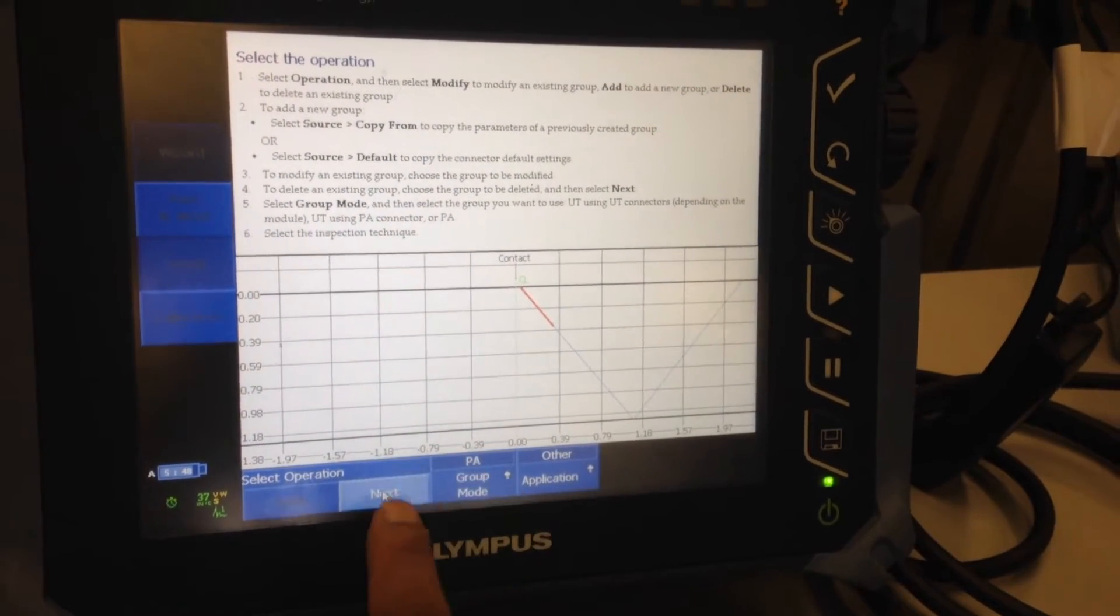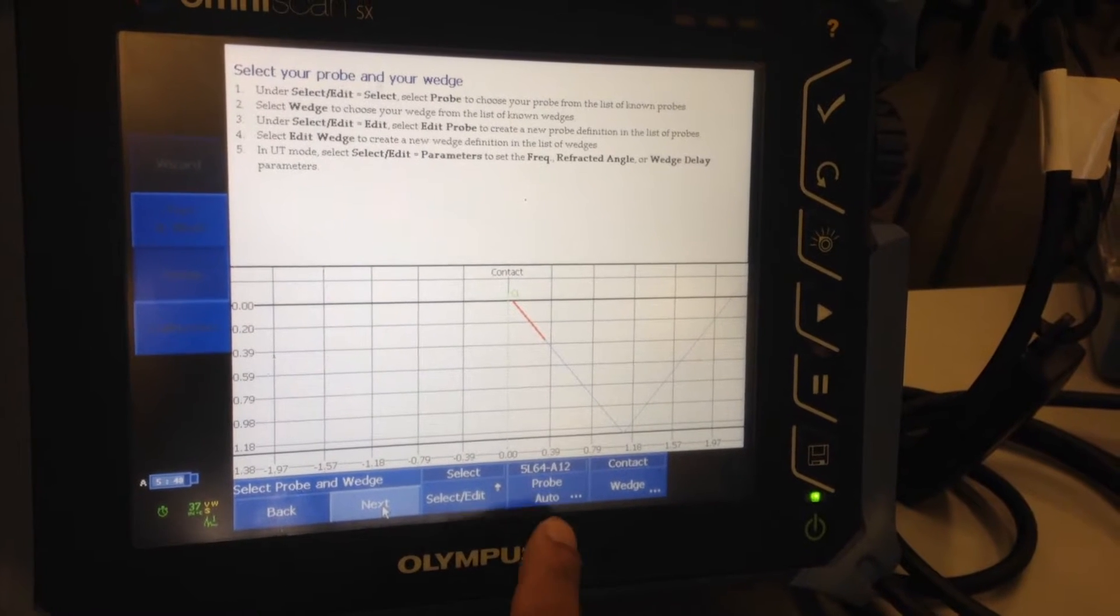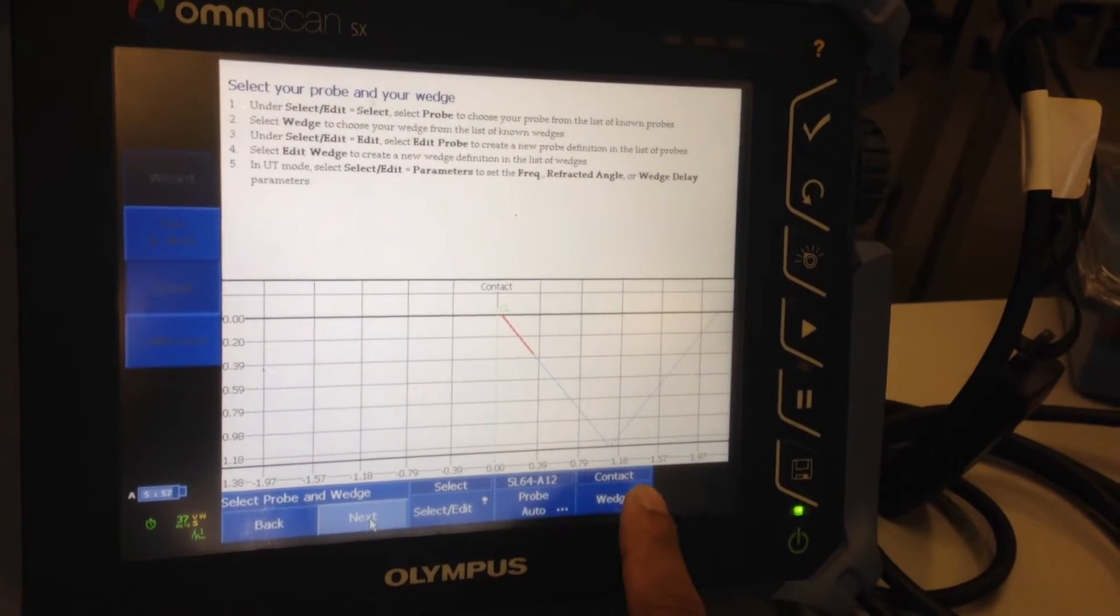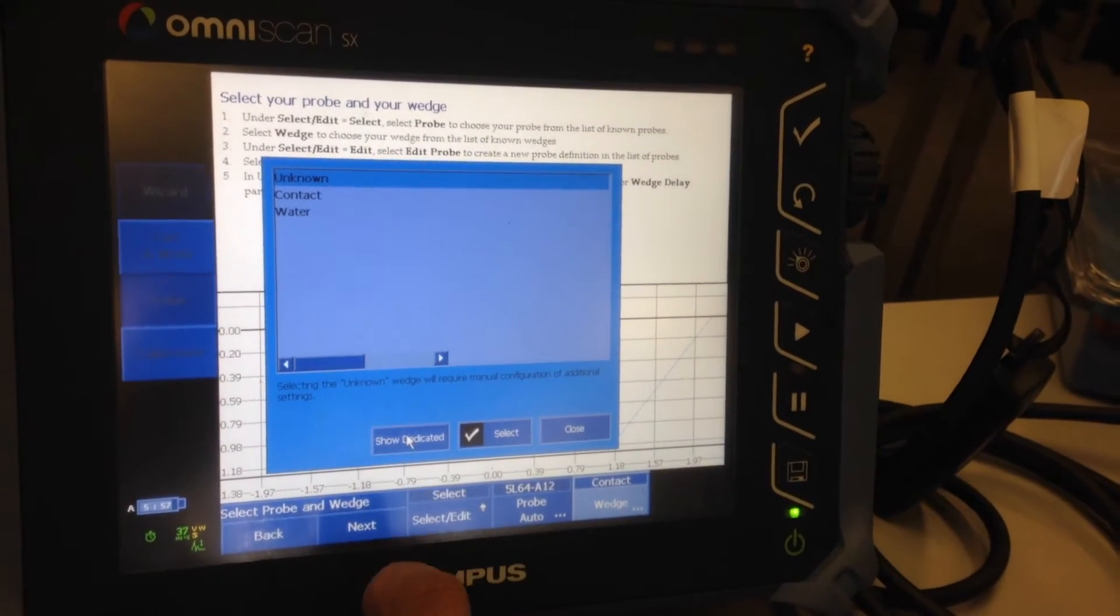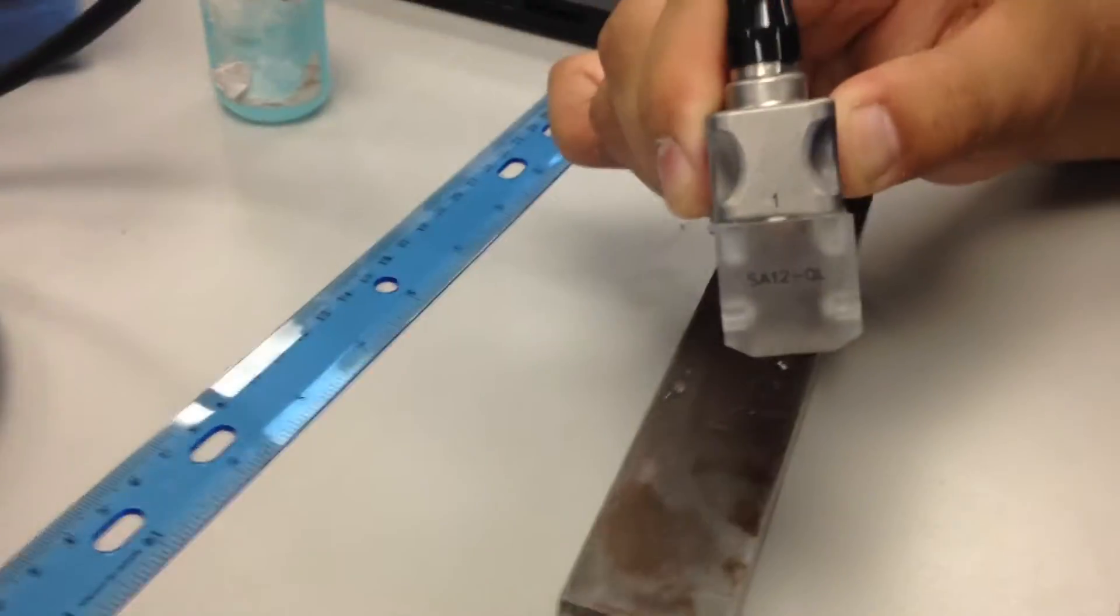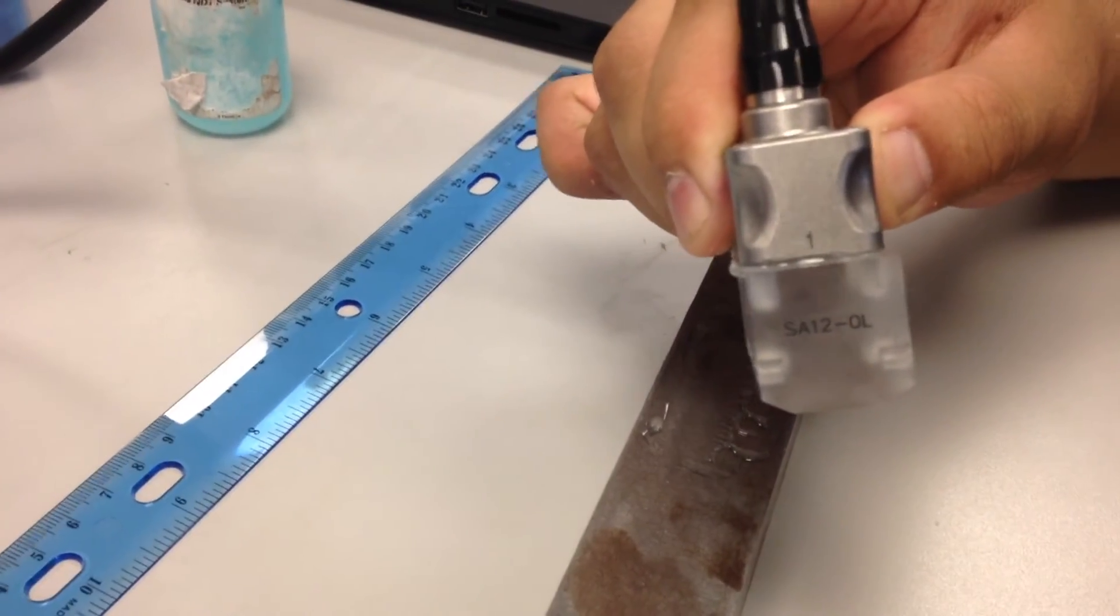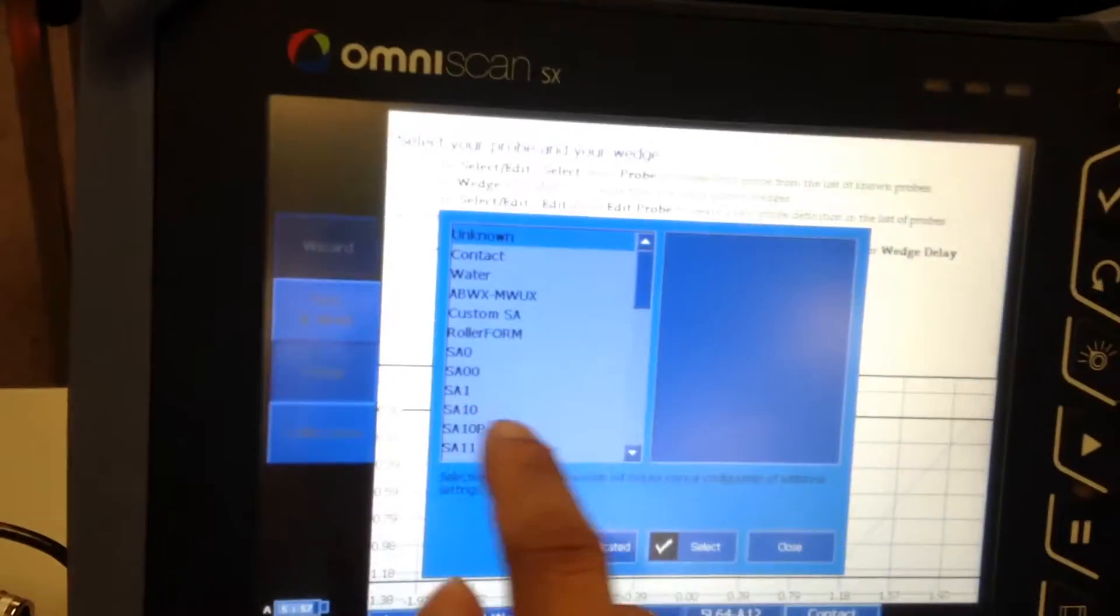Probe is auto-selected. Wedge, I click on show all so it opens up the library and read the numbers off of my wedge, which is SA12-0L. So I scroll down to SA12 and select 0L, which is zero-degree linear.